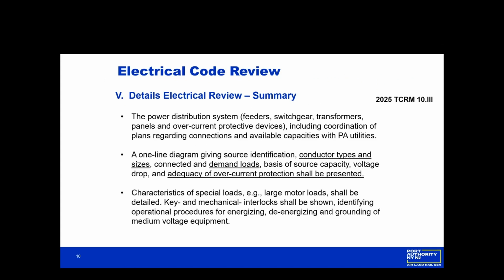The power distribution system, feeders, switchgears, transformer, panels, and overcurrent protective devices shall include coordination plans regarding the connection and available capacity with PA utilities. One line diagram, as I said before, shall show identification, conductors types, sizes, connected, and demand loads. Basis of capacity, voltage drop, and adequacy of overcurrent protection shall be presented.